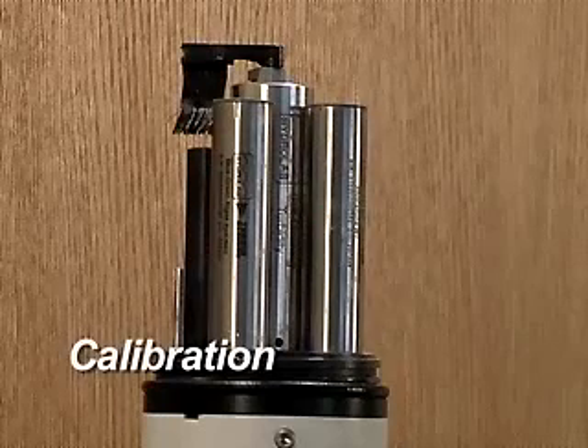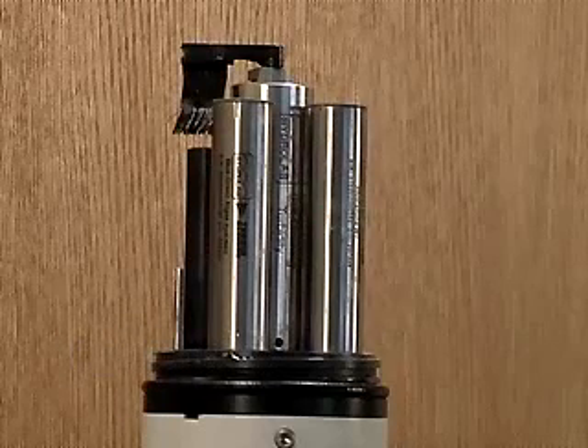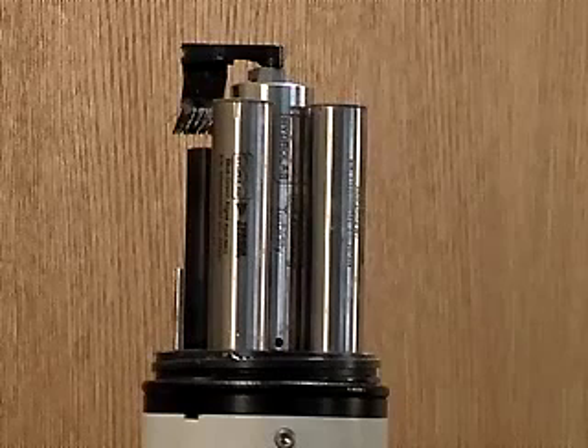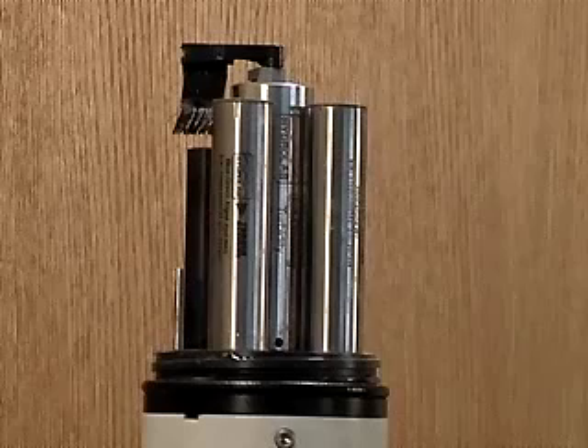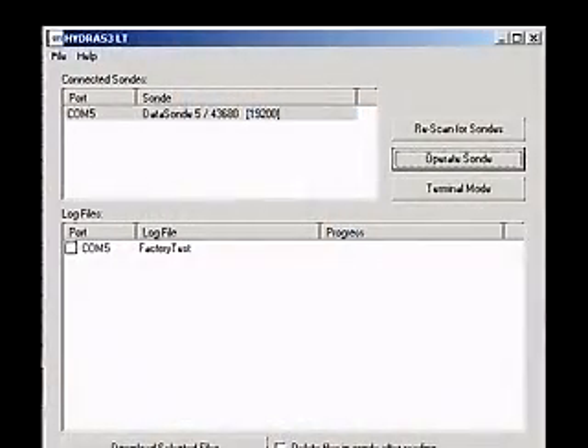Calibration. Since there is no primary standard available for chlorophyll A, the calibration process requires a sample value to be recorded, then an extraction performed to find the true value. When the true value of the sample is known, there are two methods of calibrating the sensor, with a solid standard and without. Establish a connection to the sonde with Hydras3LT.